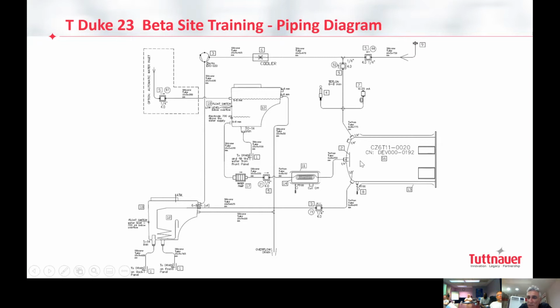And once we reach 100 kPa, the atmospheric pressure, this valve stops, the pump stops, it's not running anymore. And now we are starting again with the vacuum. This valve gets open, the chiller starts running, and the vacuum pump reaches the requested vacuum, the 20 kPa or the 24-inch mercury. And again, same concept: opening the valve, stopping the pump, stopping the chiller, closing the valve, and operating the pump by pulses, every pulse. This time you saw that the pressure went above 100 kPa, above atmospheric pressure. It reached atmospheric pressure and kept going up.